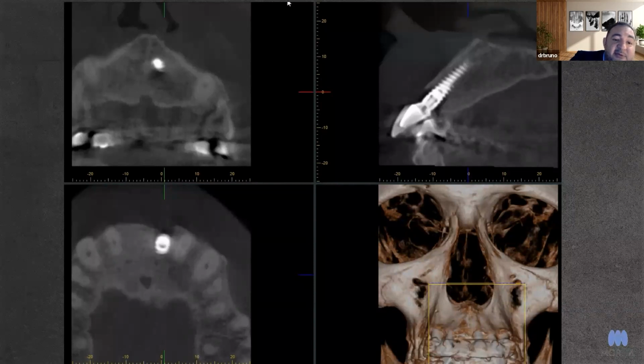Another thing too is that if you need the maxilla, for example, you can do a separate scan for the maxilla and for the mandible. And I would use the 8x8 scan in high definition with the X800 in order to avoid those artifacts. If you're going straight to the 9x8, the 9x8 acquisition is actually a 9.4 second acquisition. You're not going to have the same resolution as the 8x8 field of view.